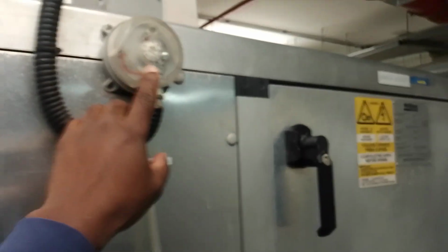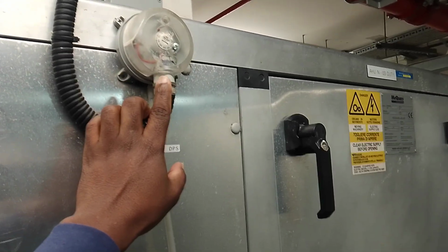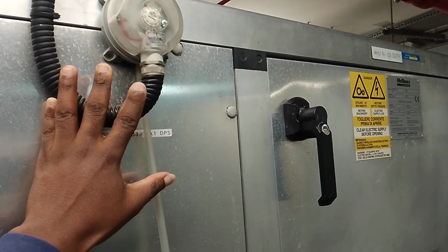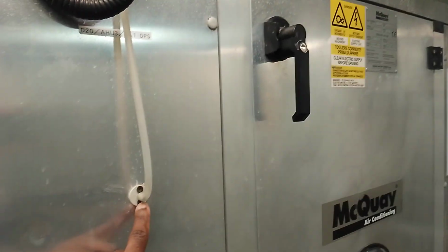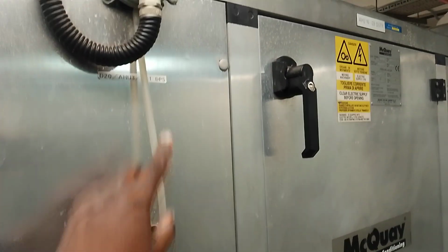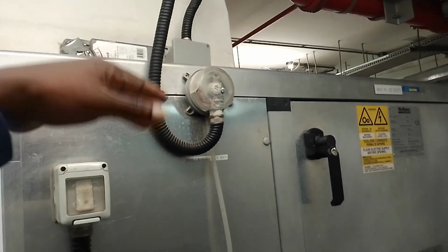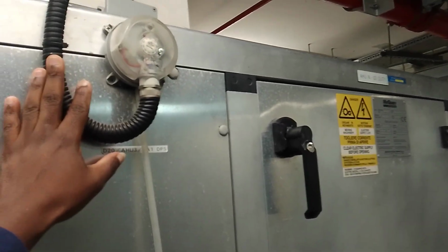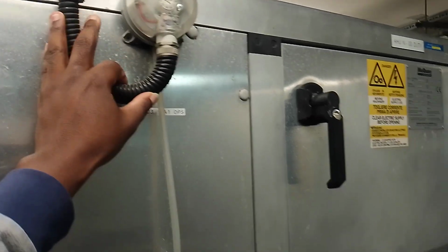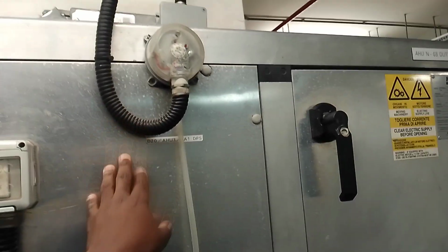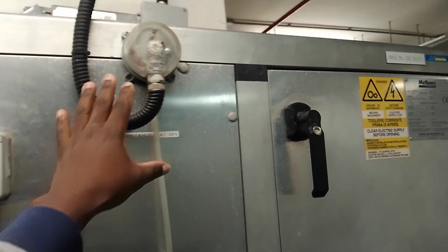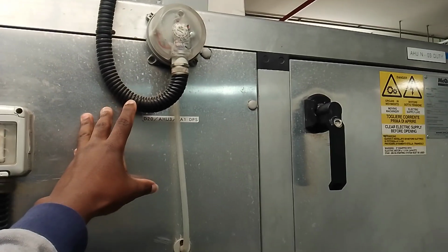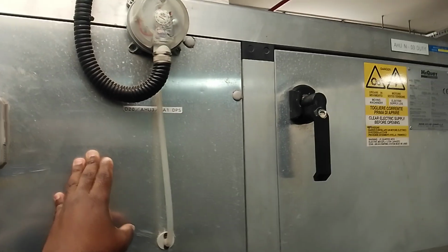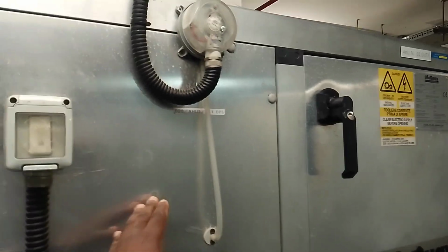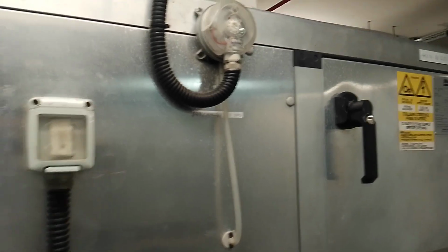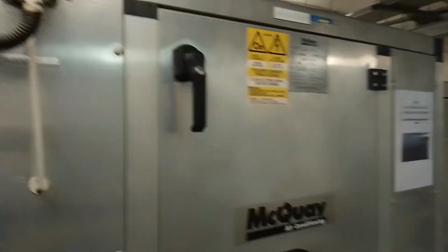This one we call the DP switch, which is controlling the actuator through the air. If there is not enough pressure, automatically it will cause the damper to go off. It is connected to the BMS. This one is for the BMS status. If there is not enough air pressure, it will send a signal to the electrical panel, that is the VFD. Then it will automatically switch off the system.